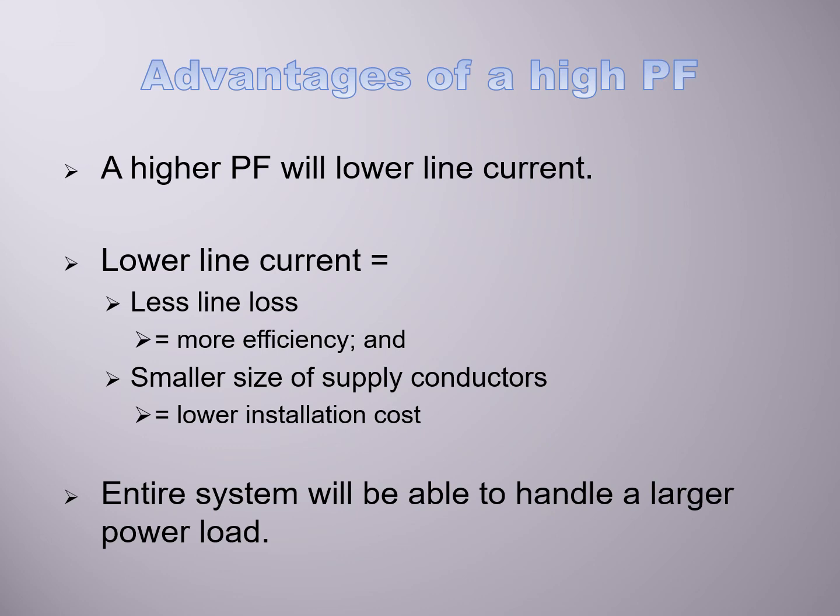The other advantage when it comes to the utilities is that the entire system will be able to handle a larger power load. Meaning if I have one building that is uncorrected, when I do the power factor correction for that building, I can actually supply two corrected buildings instead.